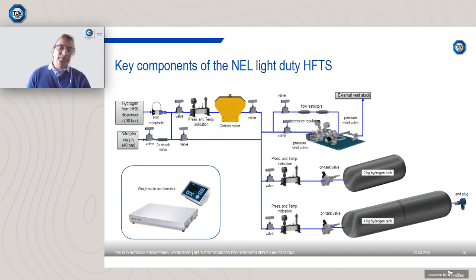There is also a pressure relief valve there, which essentially limits the minimum pressure down to 20 bar, because going below 20 bar, what you find is that it damages the tanks, as well as there are a number of hydrogen refilling stations which do not allow filling if the pressure in the system is less than 20 bar.